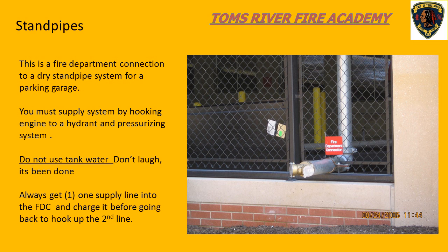This is a dry standpipe. It's on a parking garage, so there's no water in it, so you as the pump operator have to supply water. So the best way to do that is park the engine at a hydrant, hook up to the hydrant, stretch a 3-inch or 2.5-inch line to the fire department connection, get the first line in operation first, get water into the system, then go back and stretch a second line.